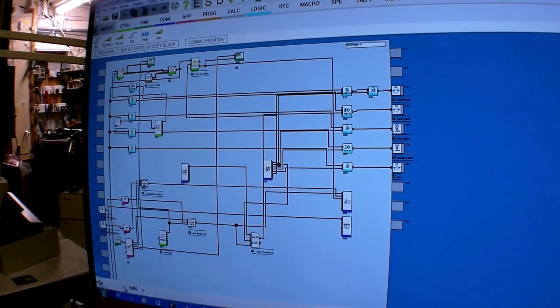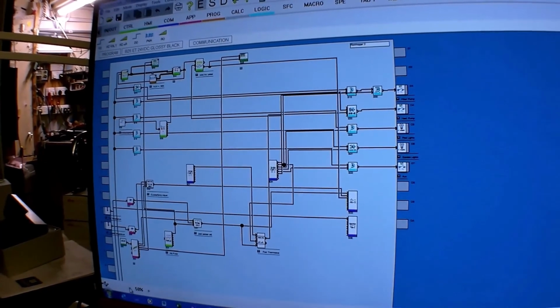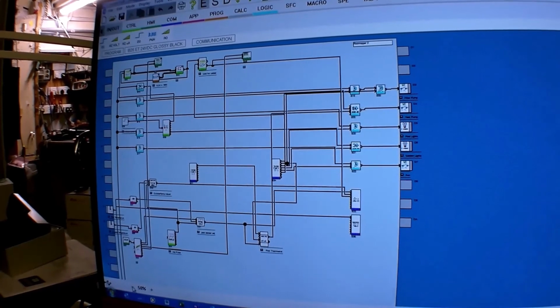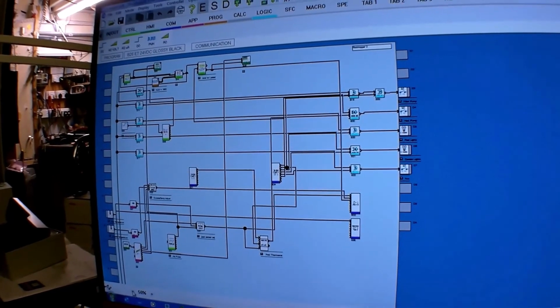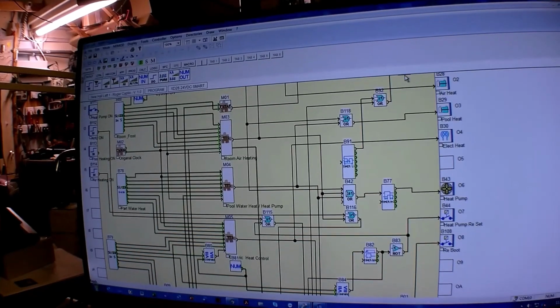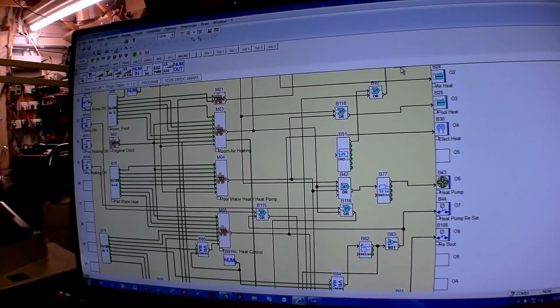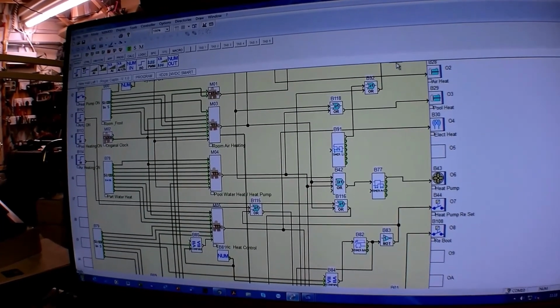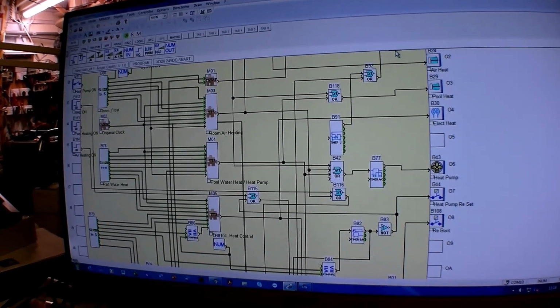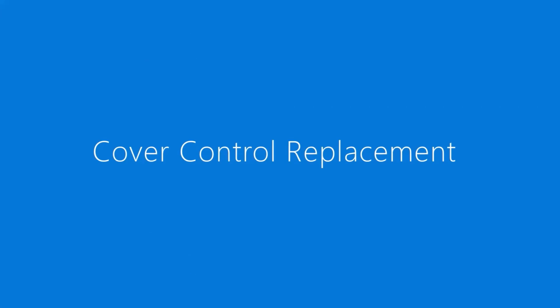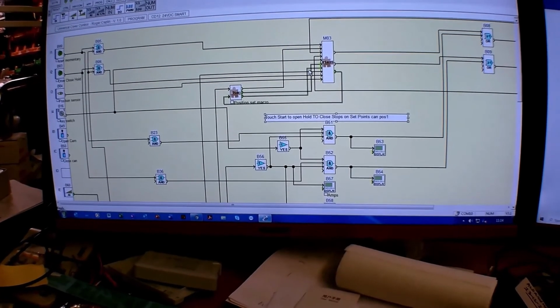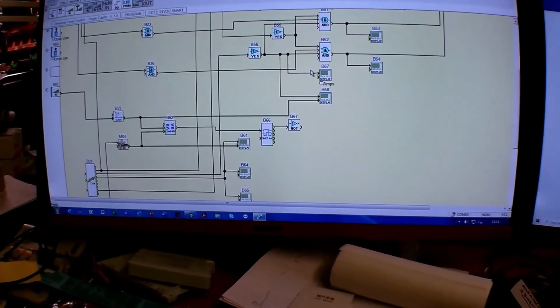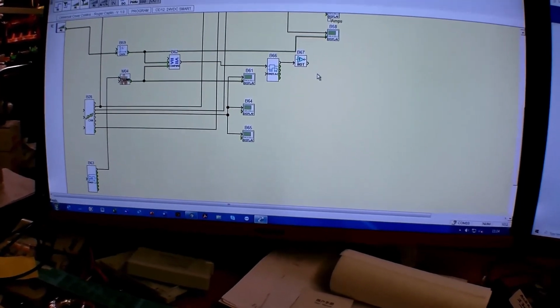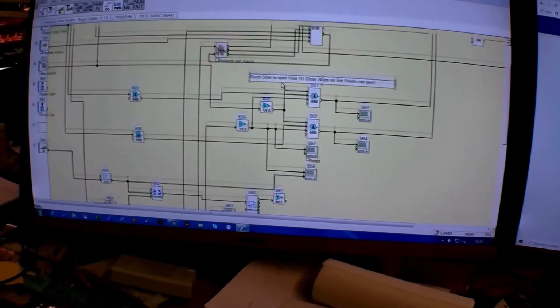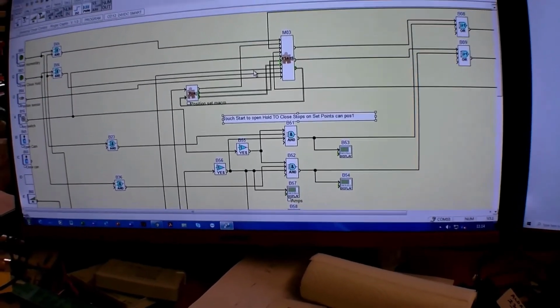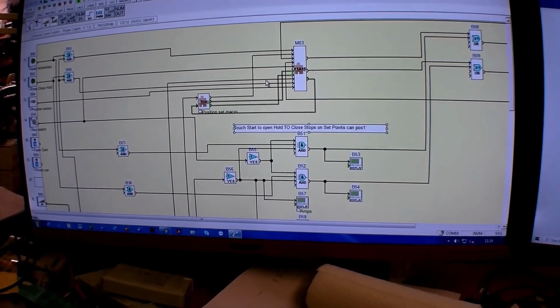This is a screen pic of a remote temperature control system with online monitoring, using an EM4. This is a screenshot of a system with heating, pumps on, remote control, flushing and purging of jet pumps, etc. This is a fairly simple circuit that is being used for a new cover control replacement. I understand that some cover controllers are no longer available for the older models, so we're making a replacement to be able to do that, and this is a first attempt at that sort of thing.